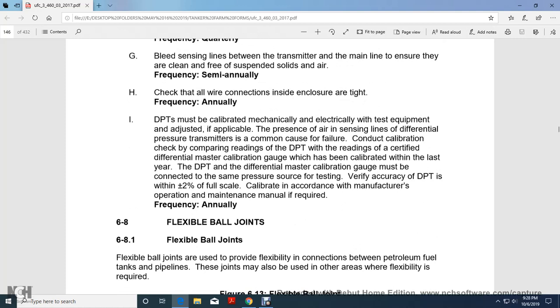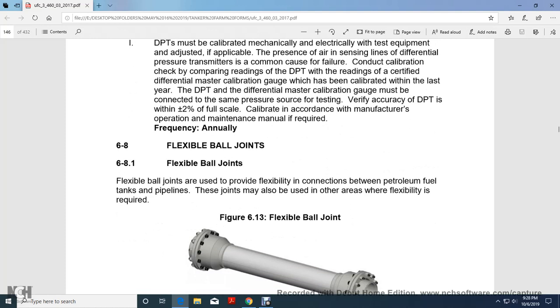Differential pressure transmitter common cause: conduct a calibration check with a comparable reading for the differential pressure against the certified differential master calibration gauge, which has been calibrated within the last year. The differential master calibration gauge must be connected to the same pressure source for the testing. Verify the accuracy of the differential pressure transmitter within plus or minus 2% of the full scale, calibrated in accordance with the manufacturer operation and maintenance manual. If required, frequency is annually.